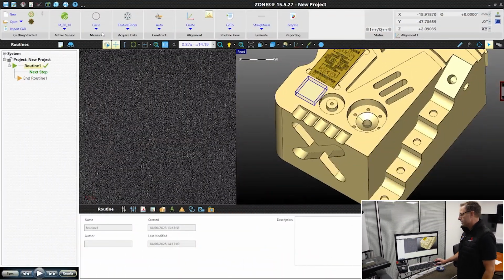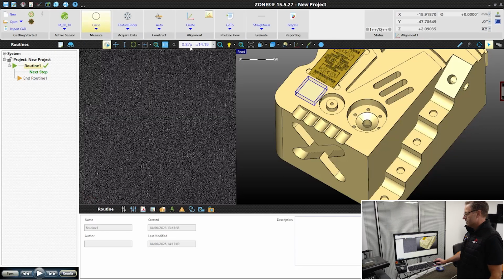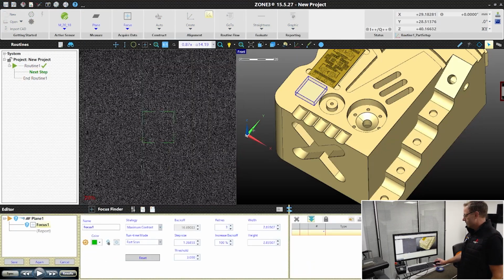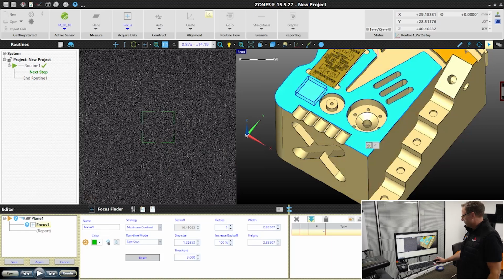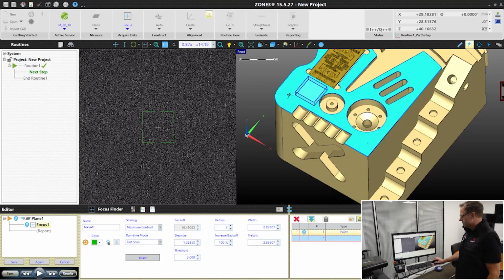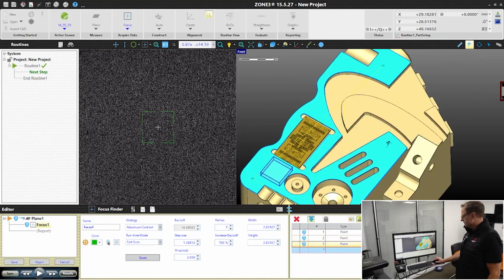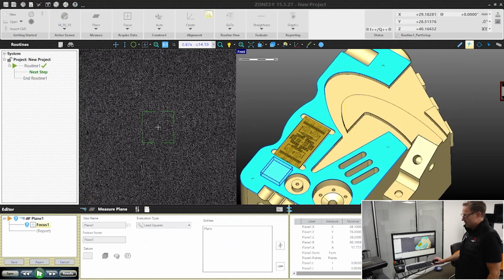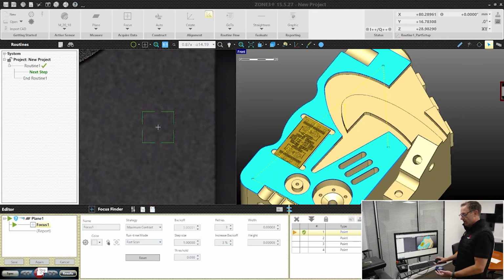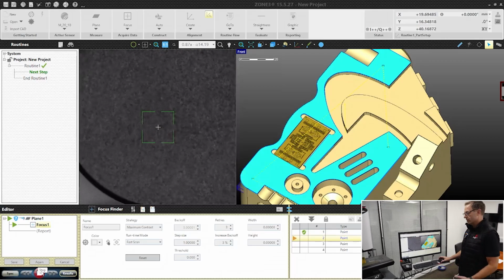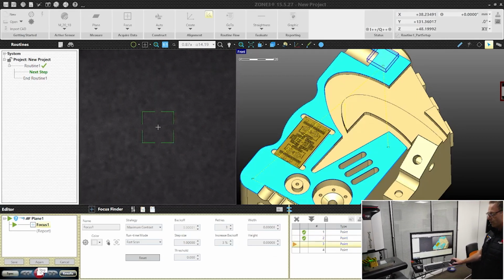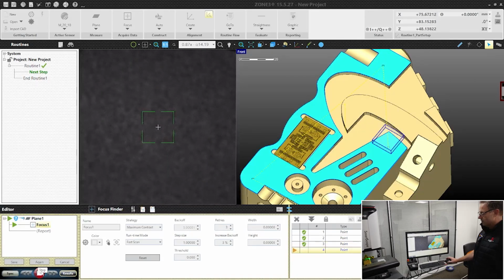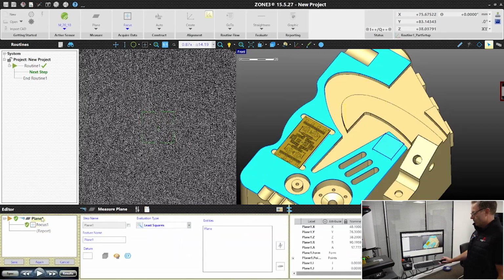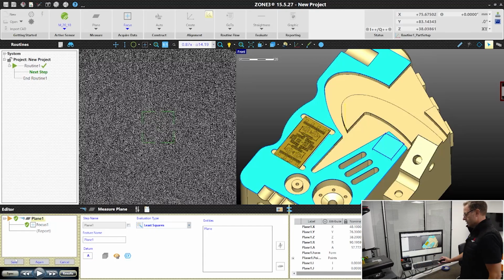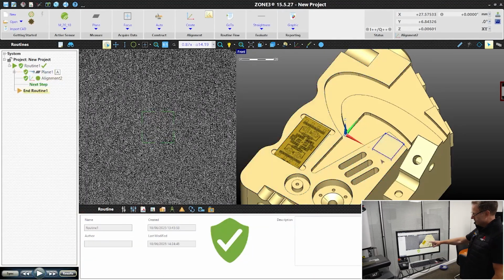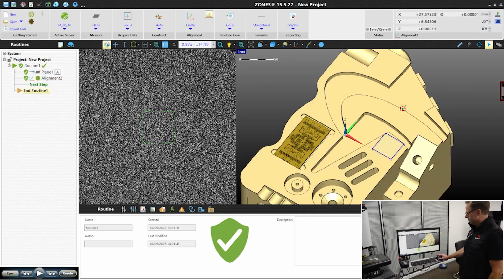If we wanted to measure a plane and set an alignment, we can tell it we want to measure a plane using the autofocus. Select that from the CAD model and then just tell it which points I want to measure just by clicking on the CAD. I'm going to select 4 points on there to define the points and then press play. You've noticed I've not had to touch the handbox at all, it's all driven straight from the CAD model. So that's auto-focusing on the face to take the points, and then we're setting that as datum A as a reference on there. Click save, and now you can see the alignment is on the top face.